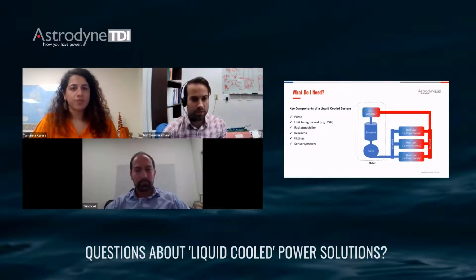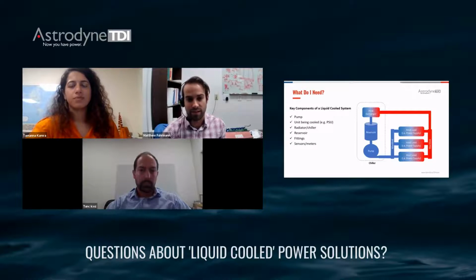First of all, power supplies can be designed in all different shapes and sizes based on the application or industry. Some key factors to consider when designing around liquid cooling would be the system flow rate required for effective heat exchange to take place, and the capacity of the pump to provide coolant to the power supply in terms of flow rate and pressure head.